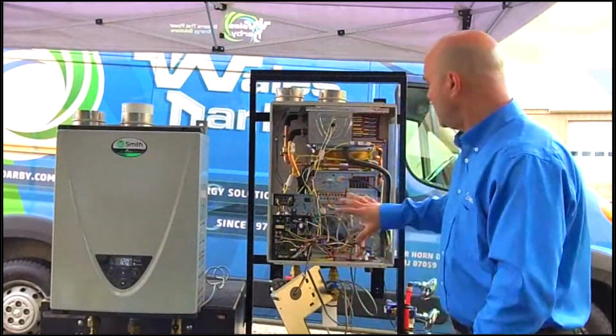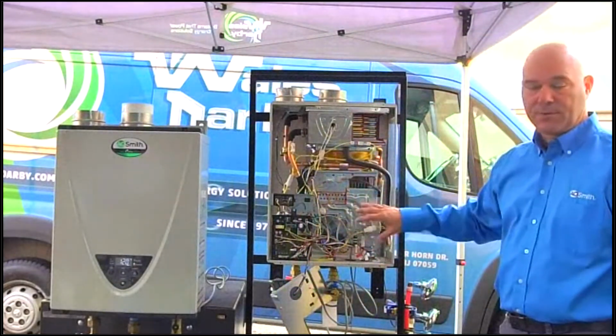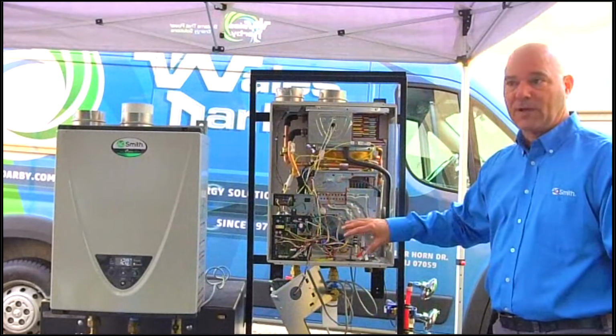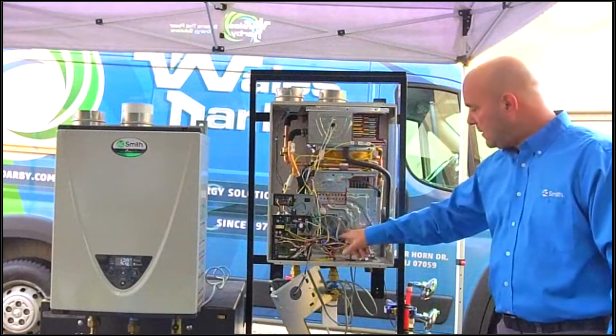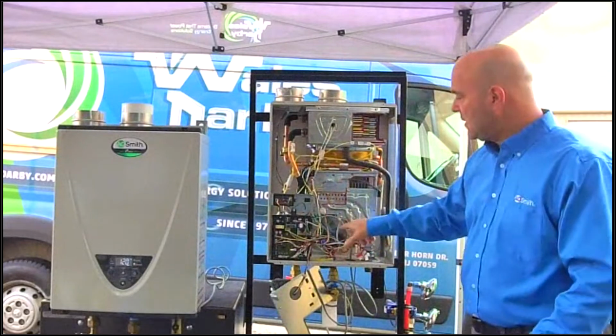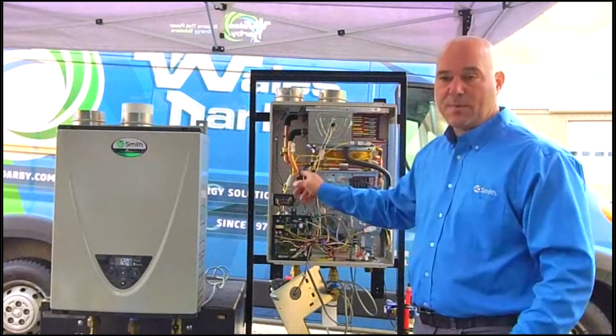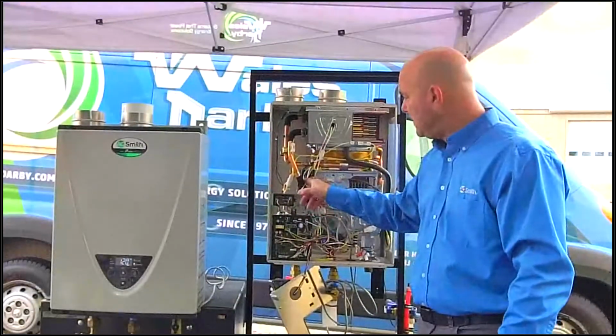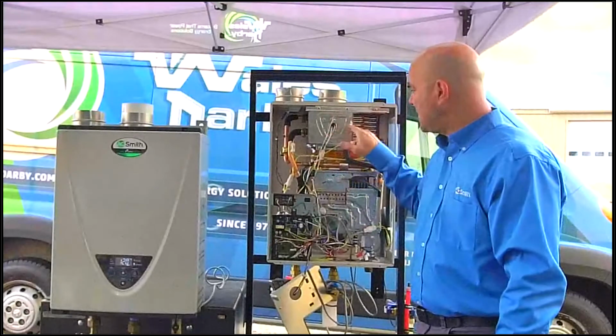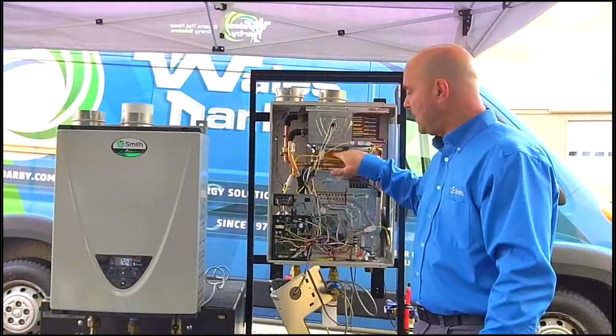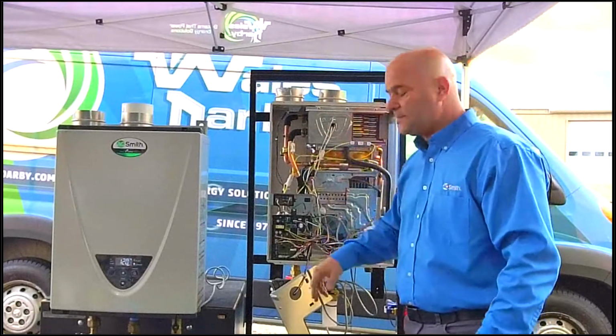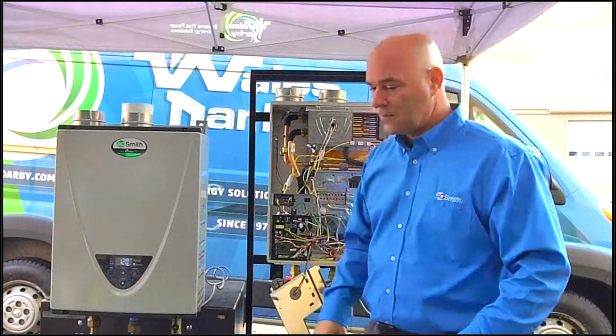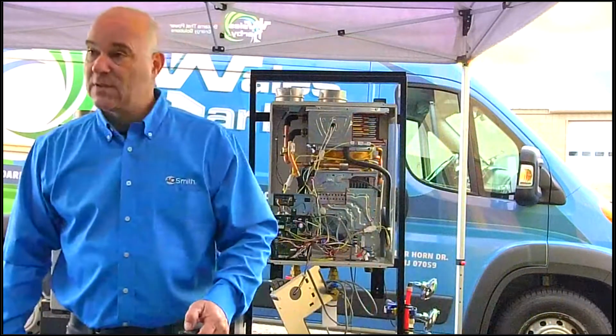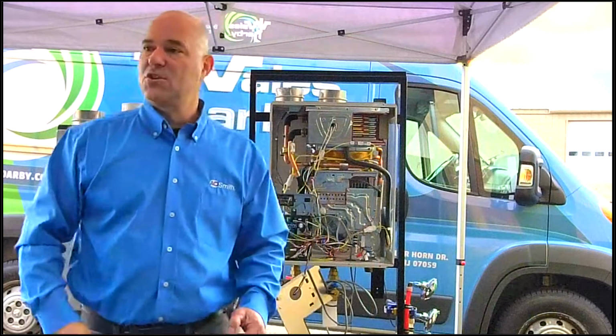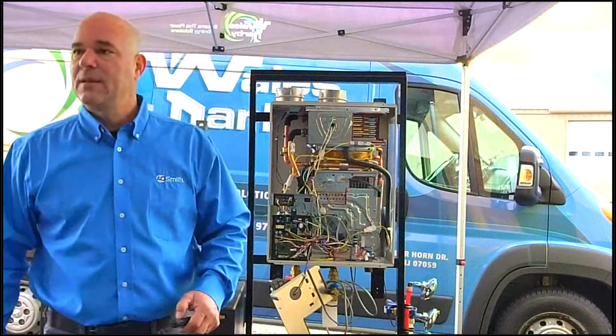So that's the water circuit through the unit. That's how the water flows. That's how the water is seen by the flow switch. On the larger units, again, that's where we mix down if need be, through the secondary heat exchanger first, back through the primary heat exchanger, out through the bottom, exiting the unit. Okay? Let me just catch up here. I got a little cheat sheet I'm looking at here on the side.